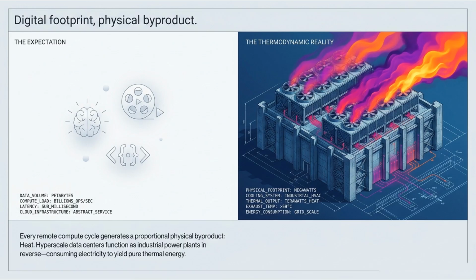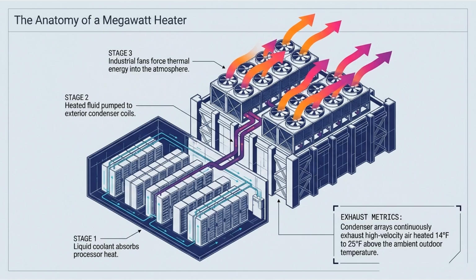And to prevent the thousands of servers inside from literally physically melting down under the computational load, operators have to rely on massive air-cooled condenser arrays. Those arrays are essentially colossal heat exchangers. They circulate a fluid or refrigerant through the server racks to absorb the thermal energy from the processors, pulling the heat away from the chips. Then they pump that heated fluid up to the roof or exterior of the building, and giant industrial fans force ambient air across the condenser coils, which transfers the heat from the liquid out into the atmosphere.